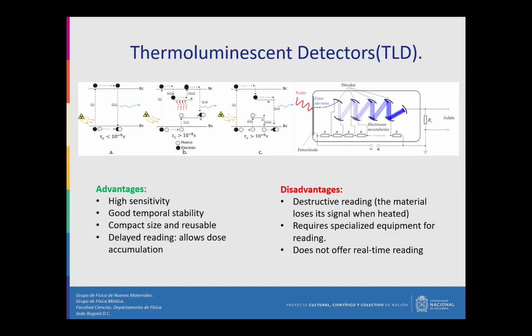Okay, thermoluminescent detectors operate through an indirect measurement, like I said before, a process based on the temporary storage of energy caused by ionizing radiation, like you see here. I have ionizing radiation right here. We have the creation of electron pairs, like I see in the semiconductors, but we don't have an electrical signal from these electrons. We have a photon signal, and we take it with a photomultiplier to get a signal.